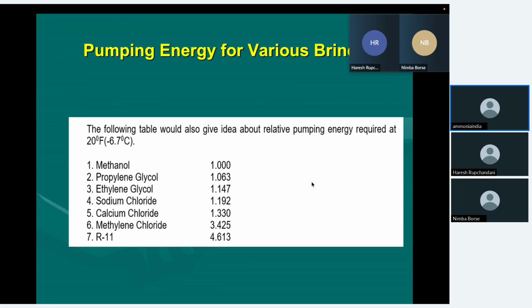Then I said, I want to see your design calculations. Please bring your file. When they brought the file, I saw they had purchased propylene glycol from one of the Bombay suppliers, and they had specified in the purchase order propylene glycol 30% concentration. But as the propylene glycol came in drums, they charged the entire propylene glycol into the system without making a 30% concentration. So 100% propylene glycol was charged into the system.